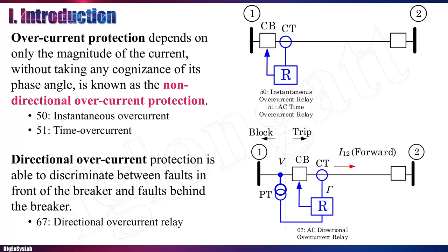In some cases, we can use the direction of the current to discriminate between fault and no-fault conditions — this is called directional overcurrent. In the ANSI IEEE standard used in America, number 50 is used for instantaneous overcurrent, 51 for time overcurrent, and 67 represents the directional overcurrent relay.